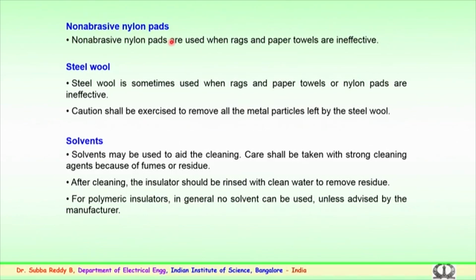So, solvents, steel wool and abrasive methods should not be employed for polymer insulators unless there is a direction from the manufacturer as to which method or which solvents to be used for the cleaning of polymer insulators. So, care has to be taken, not like the ceramic, porcelain or glass insulator. In case of polymeric insulators, the general methods cannot be used.